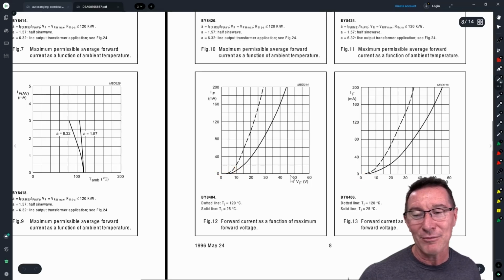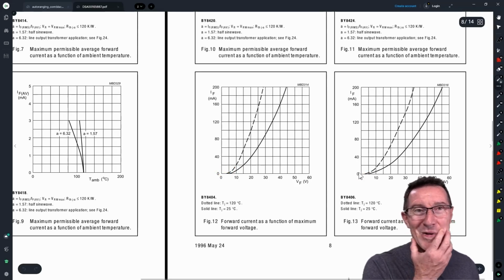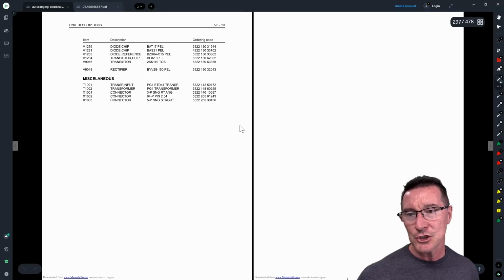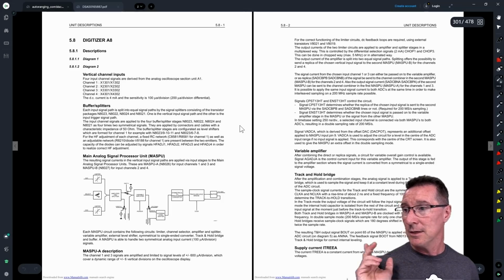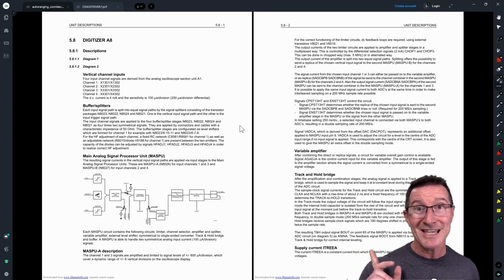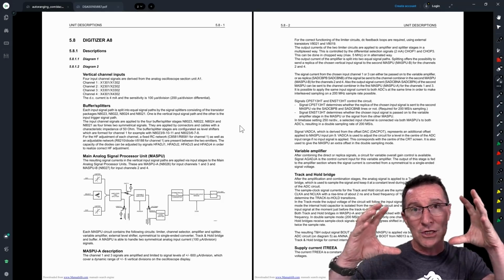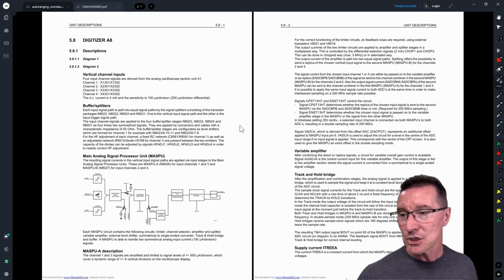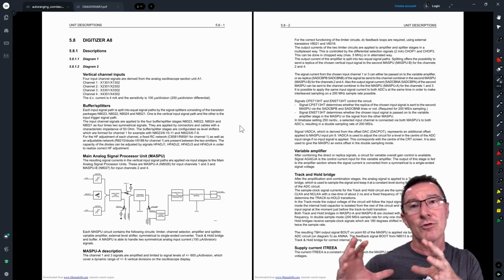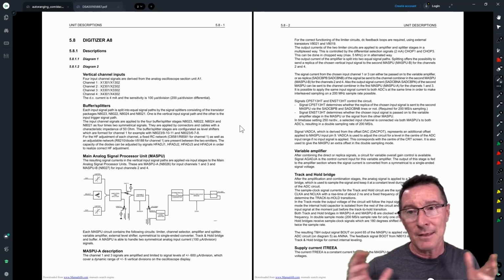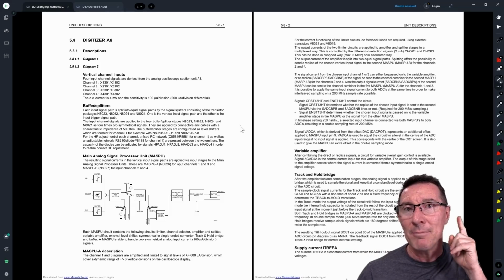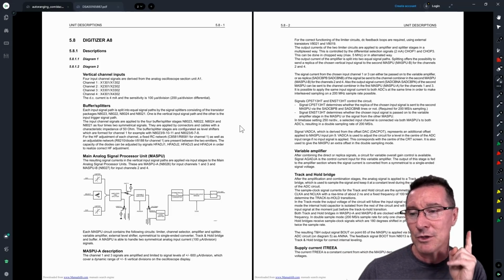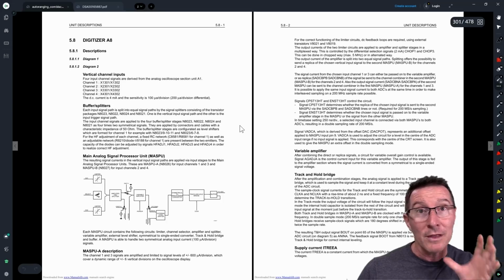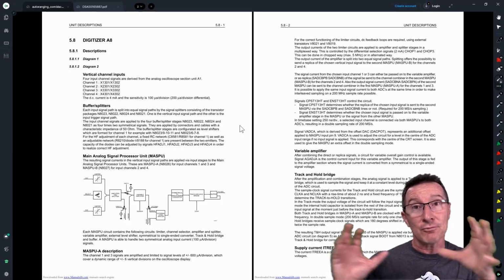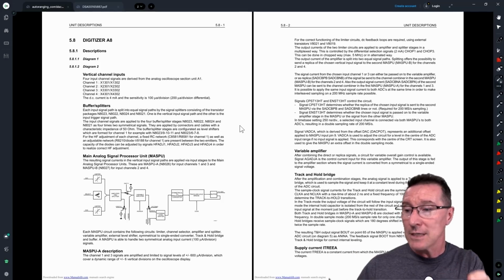I will retry that with the 121 GW. Next logical step is to reassemble it and then check, as I said, to see if the digital section is still up and running, if it's just contained to the EHT section. And then that will rule out if it's a primary side mains thing. It could be primary side mains, but I remember hearing a high frequency hum when it switched off. So all these things are important. Like all these symptoms that you get, they direct where you're going to shift your focus in the troubleshooting.